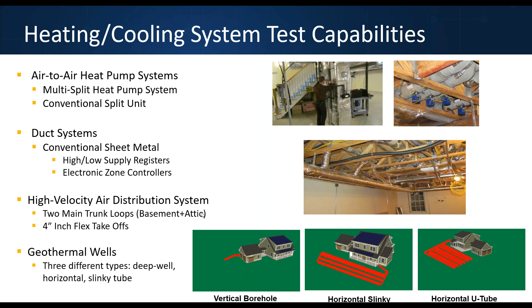One of the challenges we faced here is this home has such low loads that we really needed a small heat pump, and finding one was really challenging. It needed to be small capacity — I think it ended up being about a 2-ton unit. It also had to be really energy efficient and have special dehumidification capability. So finding the right equipment for such a low load home was challenging.